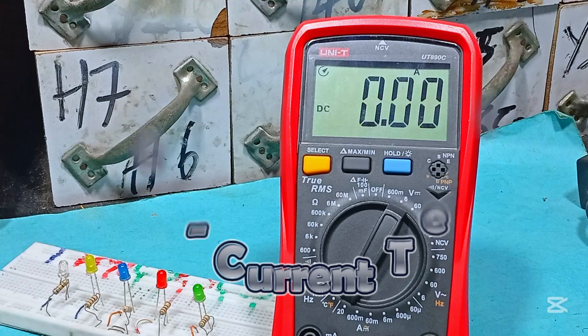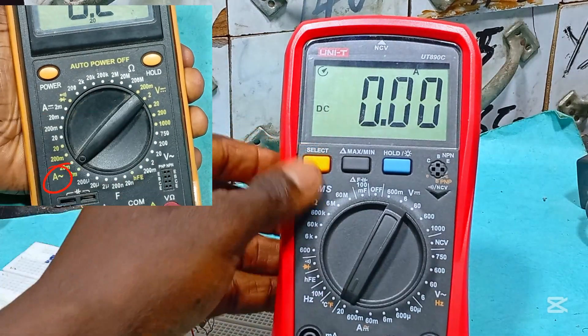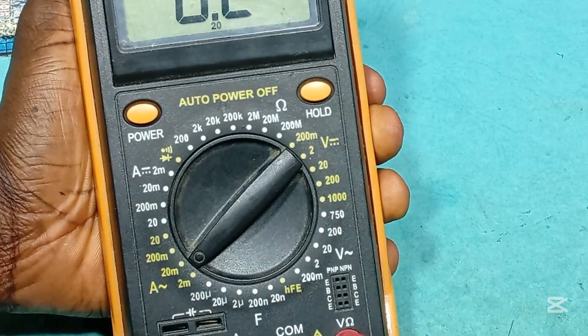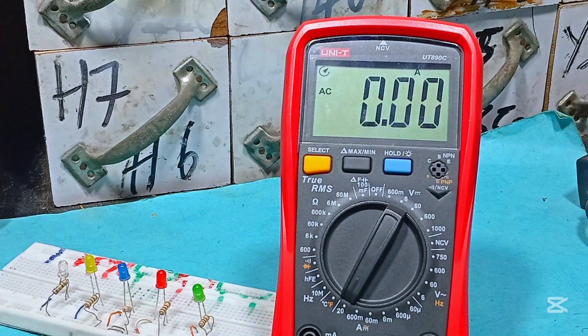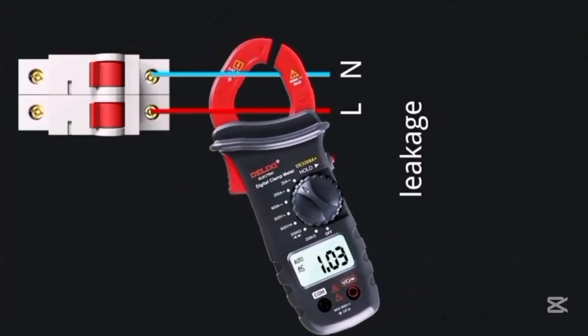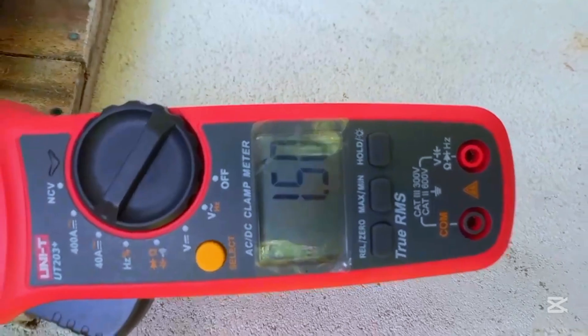To test AC current, press the select key to switch from DC to AC mode — on your meter you may have to do that manually. Using a multimeter for AC current is not safe for currents exceeding 20 amps, so using a clamp meter would be better. We have 1.03 amps reading. Clamping two wires together would cancel each other out unless there is a leakage. This load wire reads 1.5 amps of current and this other one reads 0.16 amps.